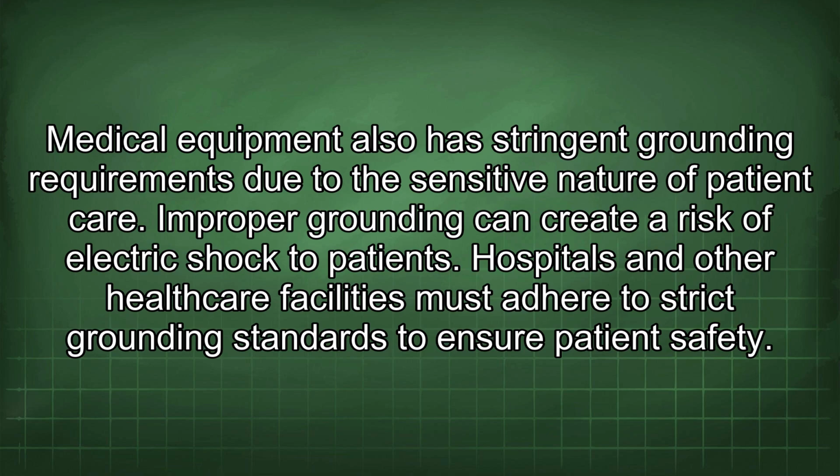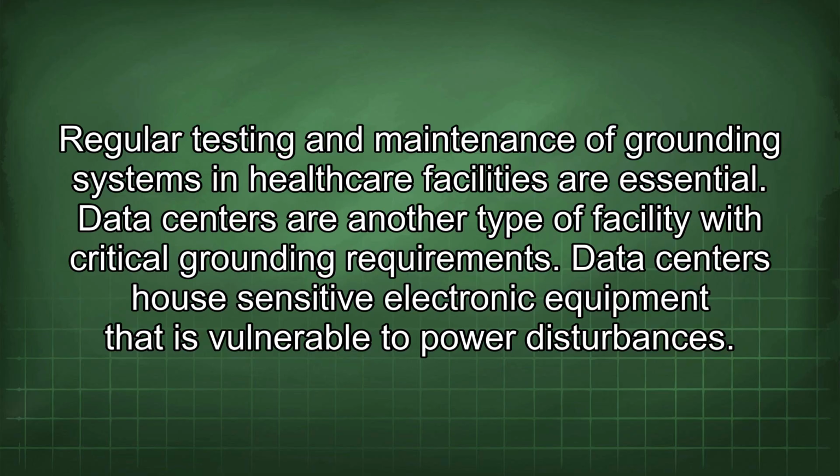Medical equipment also has stringent grounding requirements due to the sensitive nature of patient care. Improper grounding can create a risk of electric shock to patients. Hospitals and other healthcare facilities must adhere to strict grounding standards to ensure patient safety. Regular testing and maintenance of grounding systems in healthcare facilities are essential.